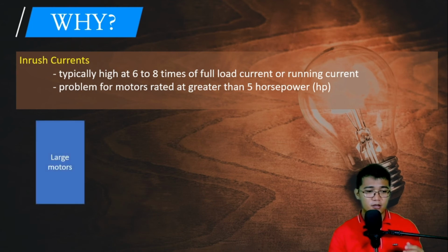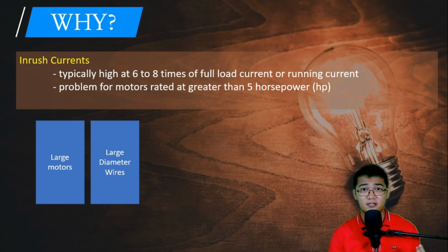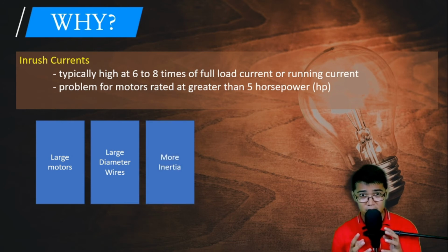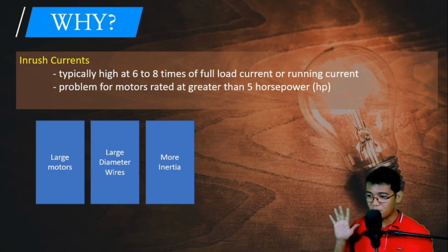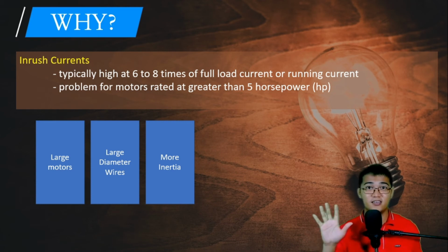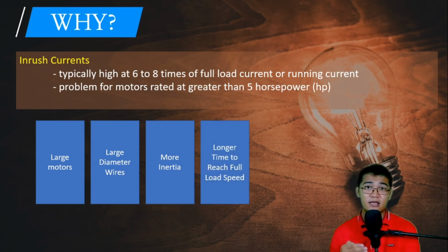Now, bakit? Large motors have large diameter wires. Meaning, pag mas malaki yung motor natin, mas malaki yung wire na gagamitin natin for the stator coils and the rotor coils. Now, pag mas malaki yung wires na ginamit natin, mas mabigat yung rotor. Pag mas mabigat yung rotor, binabanggit natin dito more inertia. Inertia meaning the tendency ng isang bagay na hindi gumalaw. So, given yan, na pag mabigat, sample, tulak natin yung mabigat na tao, mahihirapan tayo. Compared kung payat yan, matutulak natin yan. Meaning, it will take time for our motor to reach its full load speed.